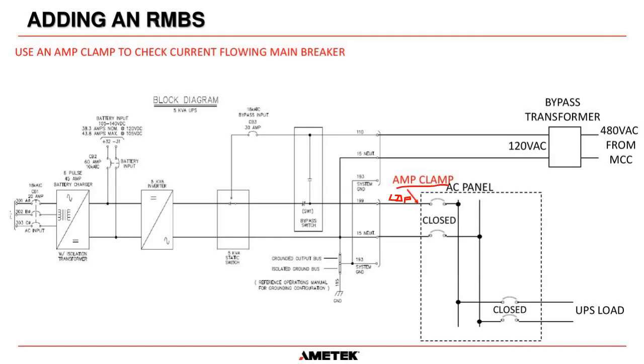Okay, it's very important we know that for 2 reasons. First of all, on the next screen, you're going to see we're going to install a temporary backfeed breaker. And later on, we're going to make sure that when we do go over to that backfeed breaker, all of the load is on there before we open this breaker here. It will become self-explanatory as we move on. Okay, so first things first, we need to know how much current is in there and then write it down so you know that you have that available.